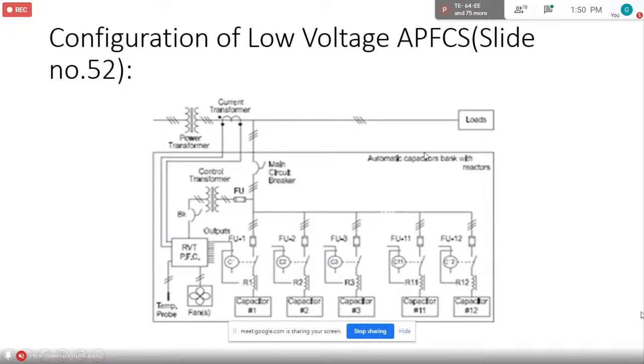And there is a fan provided to keep the temperature within limit. Not a very good idea, because if the fan fails, the capacitor will cook and die. So ask for a capacitor unit which will work without a fan. So we got voltage supply from here, current supply from here, and then it senses the power factor, straightforward. And this is the group isolator.